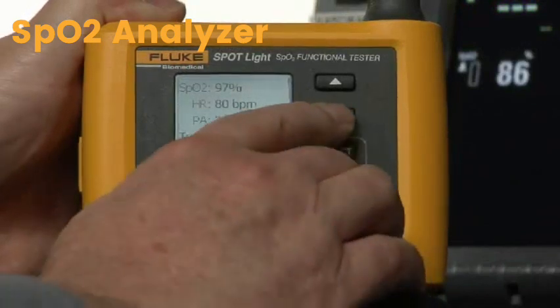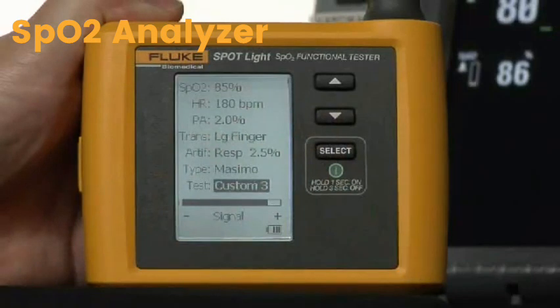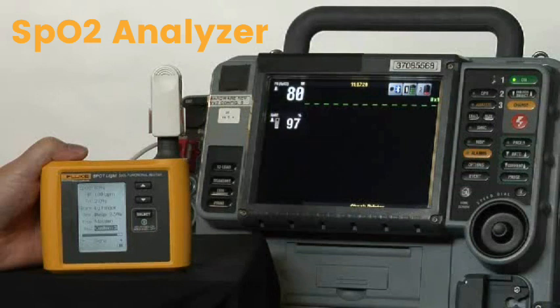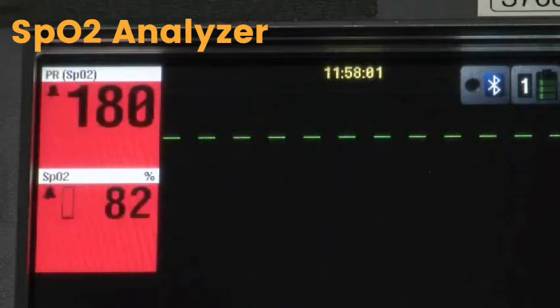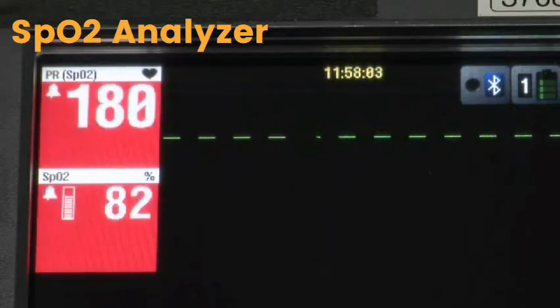We're going to go to our custom setup and go to custom 3, which is programmed for a patient with a high heart rate and a high O2 sat. See, it sets off the high limit alarms, which is exactly what we want it to do. We'll watch till the oximeter reading and the heart rate settle.